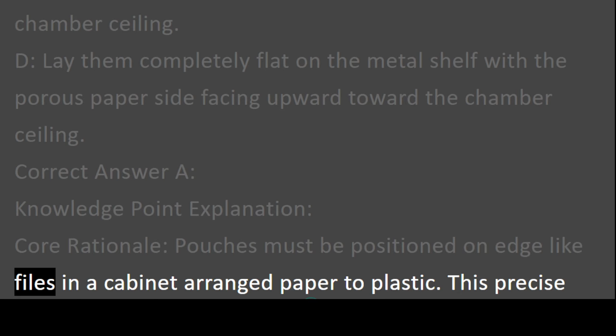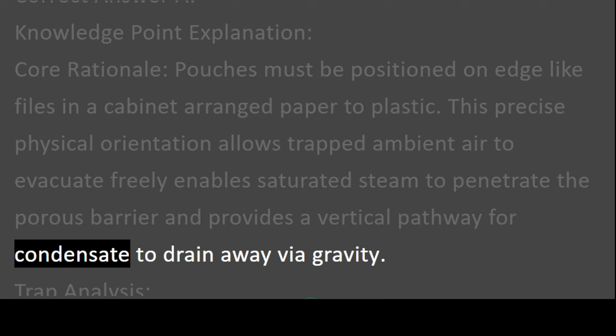Correct answer A. Core rationale: pouches must be positioned on edge like files in a cabinet, arranged paper to plastic. This precise physical orientation allows trapped ambient air to evacuate freely, enables saturated steam to penetrate the porous barrier, and provides a vertical pathway for condensate to drain away via gravity.